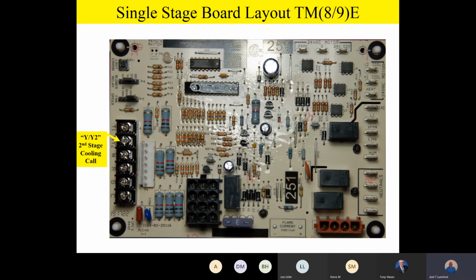Now, because this is a single stage heating board, we're only going to have one W terminal for heating. And sure enough, that's what we see. W is our heating call. R is 24 volt hot. And again, this is pretty standard in the industry. I think you'd expect to see that in the industry. R is 24 volt hot. G is our fan call from the thermostat, asking for fan operation. And C is 24 volt common.